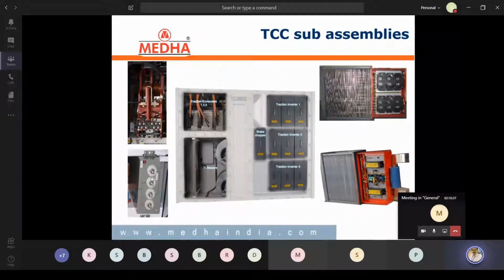This is that DC link contactor, the offload switchgear contactor. There is a servo motor driven contactor, and there is a DC link capacitor bank, one for each inverter. It acts as a filter: if there are any AC ripples in the DC link path, it will suppress them. To provide pure DC to the inverter modules, this capacitor bank is placed. Even this capacitor's temperature will be monitored by providing a PT100 probe.